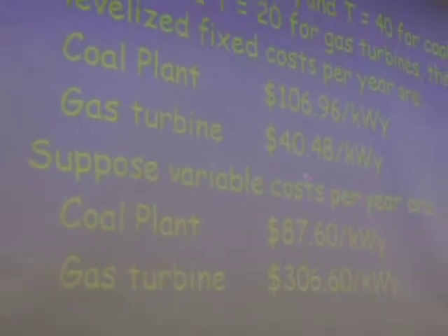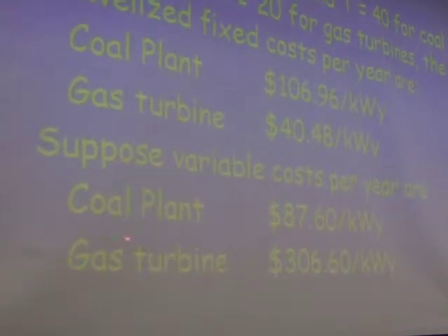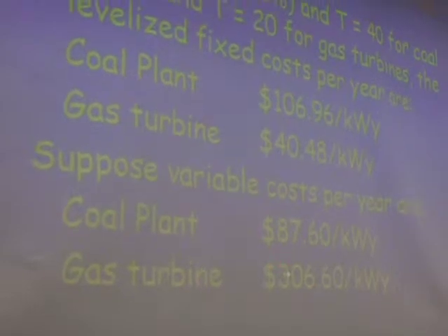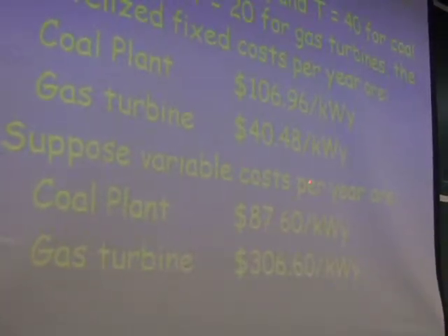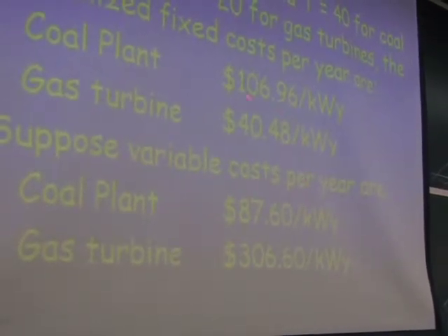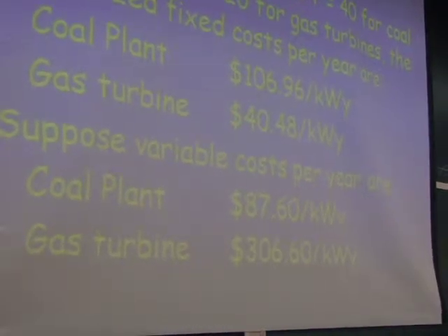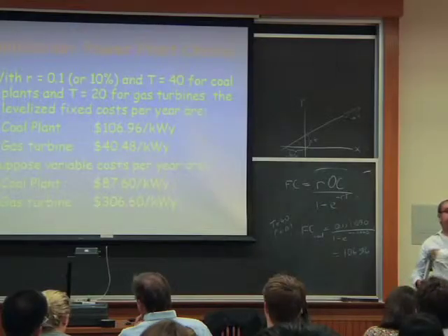And that's how much your total cost would be. You'd take 40 plus 306, if you're running the gas turbine all the time, and you'd get a number like 346. And that'd be your total cost of operating the gas plant, right? So obviously, if you were running it 100% of the time, 190 is less than 346, so you'd go with the coal plant.